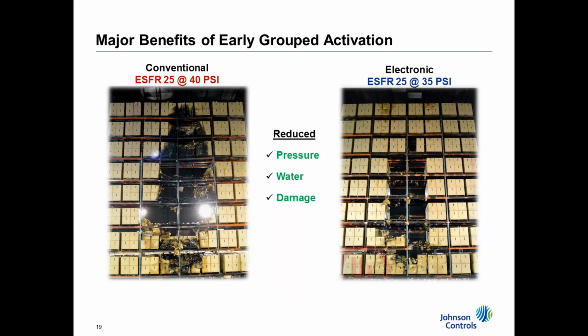Okay, again, this is just the major benefits of the early grouping. If you look at the left-hand side, that's a K25 sprinkler. So if you go to electronics, you're using less water pressure. You're going to have less water damage. You're going to have less residual damage on adjoining commodities from water damage, because you're controlling that ring to where you want that actuation to be.